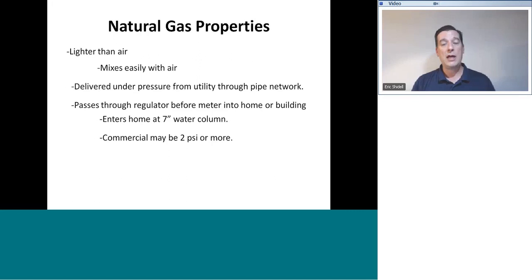In commercial applications, natural gas lines that are greater than 7 inches of water column must be labeled, and they may be labeled with a label that says, such as medium pressure gas. Medium pressure gas normally means 2 pound gas, or it may be labeled with an actual PSI that's in the pipe. So be aware of that.